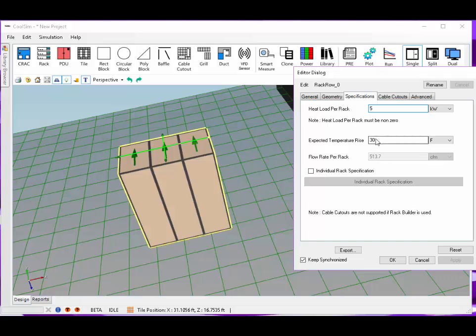You notice the flow rate is changing as I change the delta T. Smaller delta T's will give you higher flow rates. The relationship is just about 154. You see there, CFM per kW. That's what satisfies the convective heat transfer equation for 20-degree delta at sea level. If you change your density, change your elevation, these numbers will change a little bit, but at sea level, that's how it behaves. So let's put in 3 here. 3 is a normal number, or 4, 5, something like that.